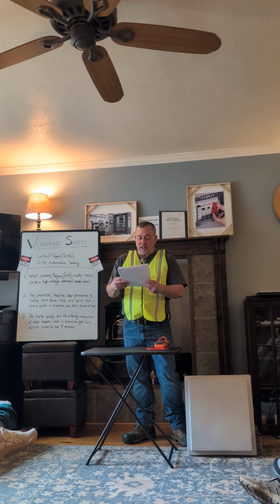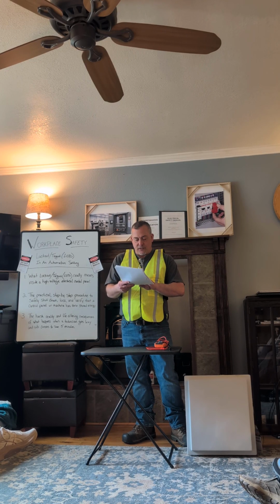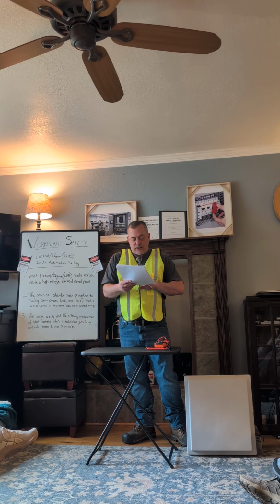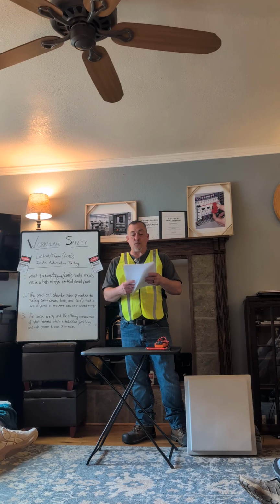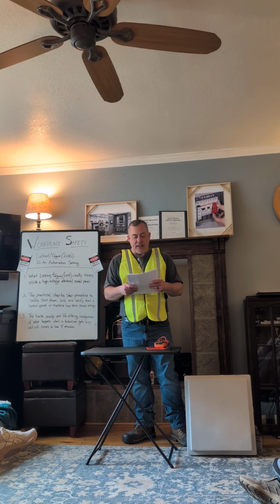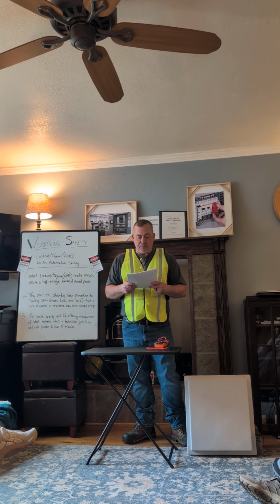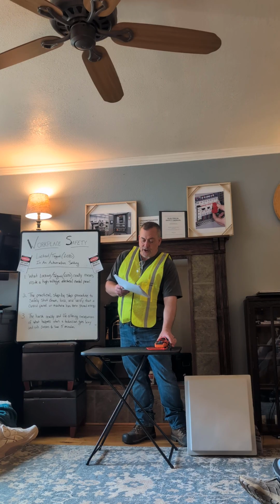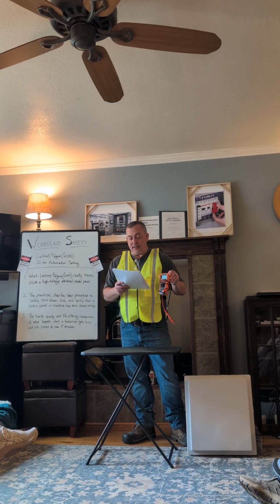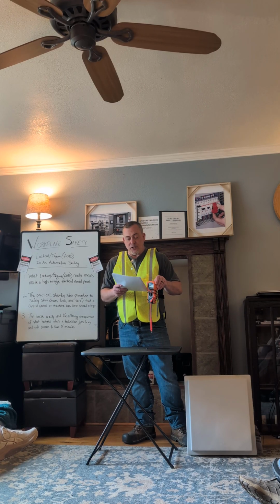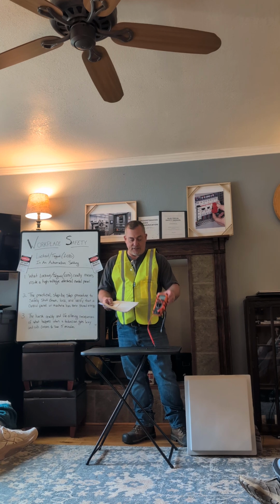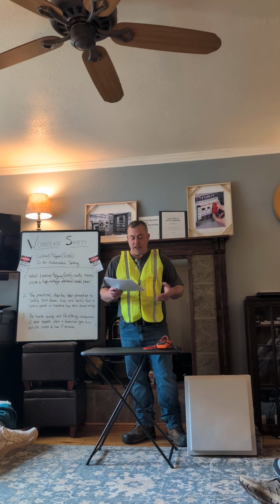Number 7, test for dangerous voltage between all relevant conductors, especially those you could physically contact. This includes measuring between pairs of phase conductors in a polyphase system, as well as between each phase conductor and earth ground. Number 8, confirm the proper operation of your voltage meter again against a known source to ensure your meter didn't fail during that test and show you a false 0 reading.